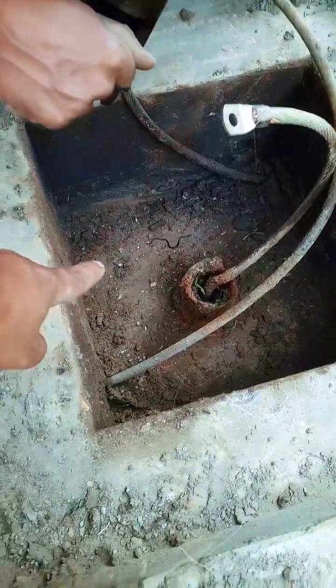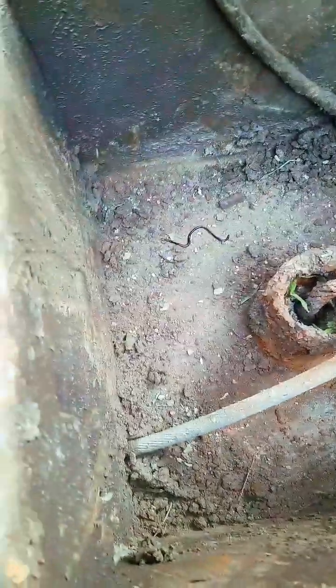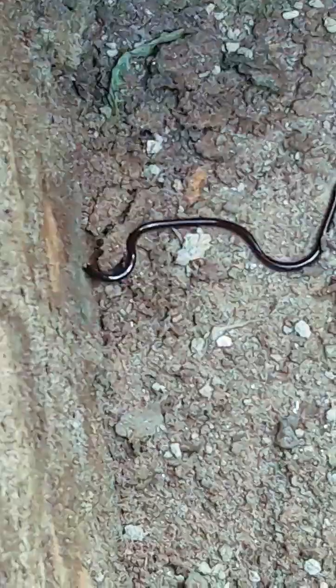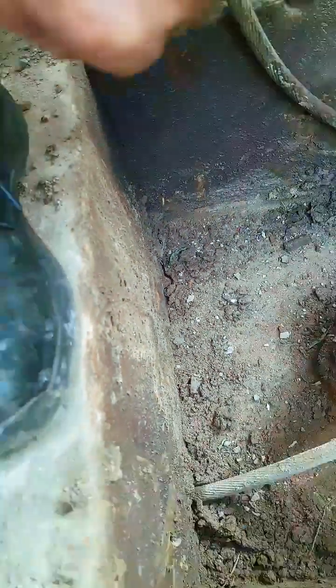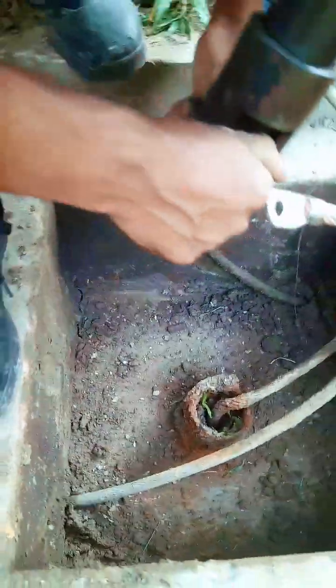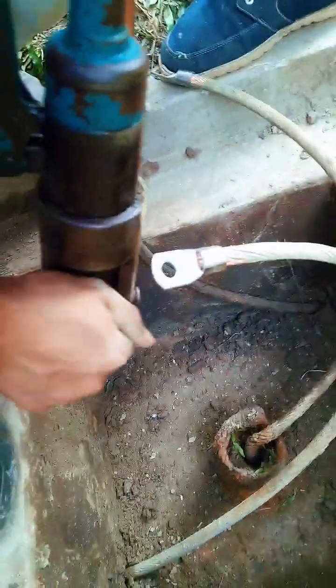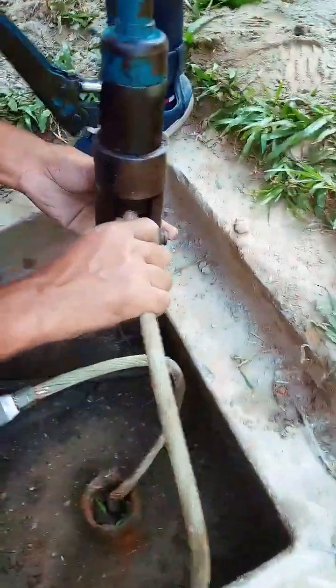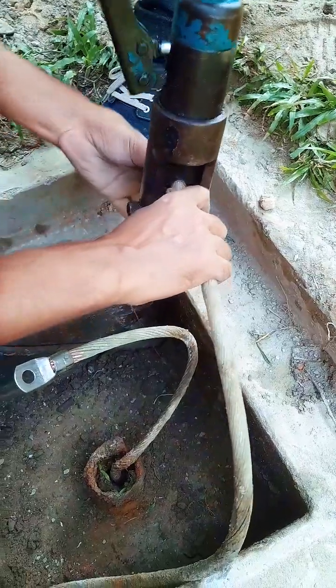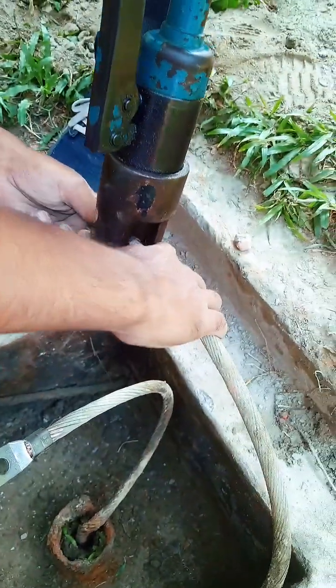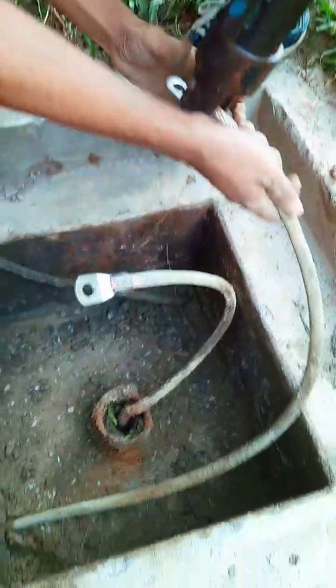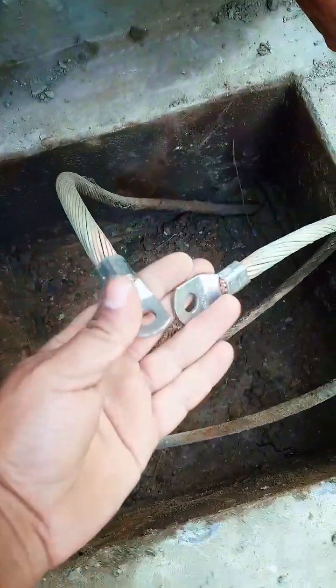New joint installation. After surface preparation, we installed a brand new copper lug. We tightened the joint using a fresh nut and bolt set. The conductor was mounted to the earthing busbar securely, no loose play, no movement. A mechanical joint must always be press tight. If not, micro sparks will happen during heavy current flow. This can burn the lug, damage the conductor, or even melt insulation.